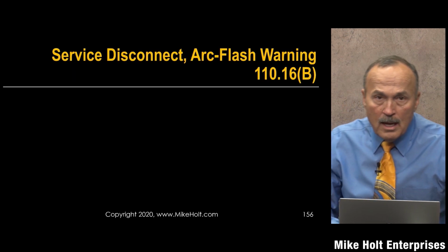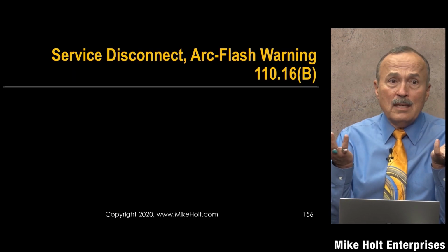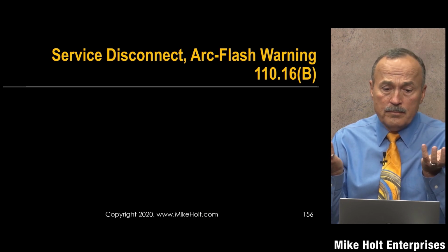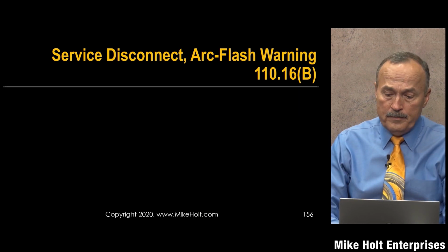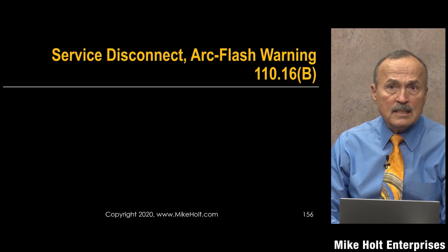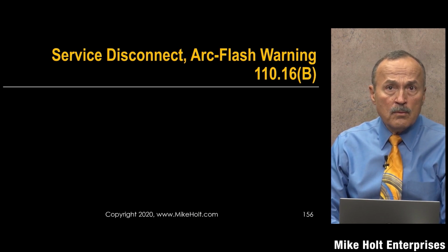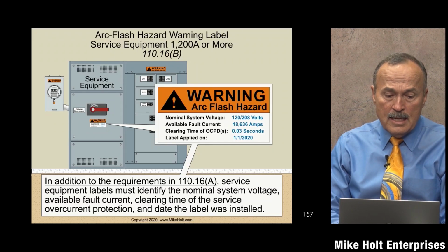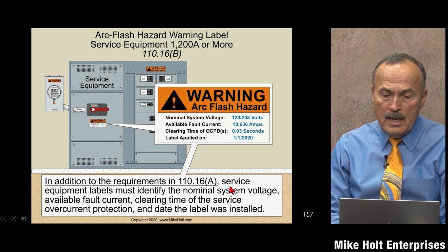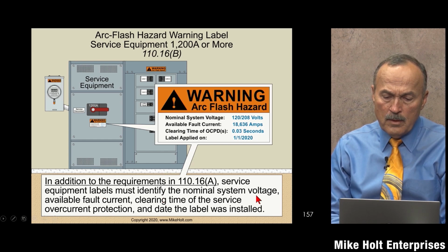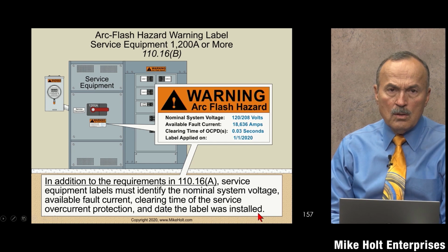All right, so now we need to have a warning sign, and it's supposed to tell us about this, but it really doesn't accomplish a whole lot. Now let's go to service disconnect arc flash warning, 110.16(B). It says that in addition to 110.16(A), which is the arc flash hazard warning part, the service equipment label must identify the nominal system voltage, available fault current, clearing time of the service overcurrent device, and the date the label was installed.